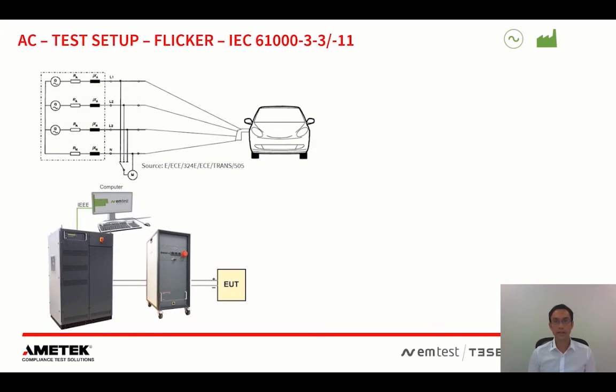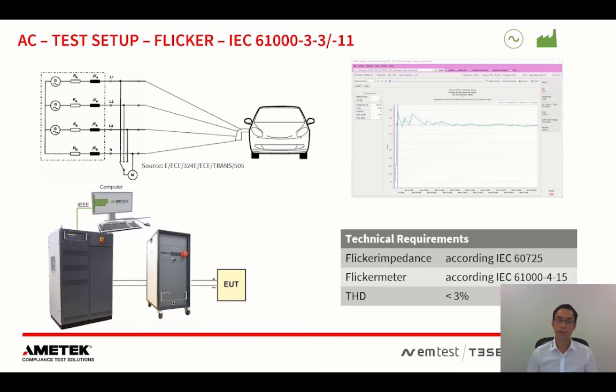The second test I want to highlight here is the flicker test, or voltage variations. It's a similar test setup to the harmonics, as you can see on the top left. Again, we have a three-phase or single-phase source that provides a very clean AC signal. We also have a measurement device, which is shown with the little M in the circle there. The measurement device, the so-called flicker meter, needs to be according to IEC 61000-4-15. There it is also very clearly specified how the flicker meter needs to measure. And then the special thing for flicker is that we have a so-called flicker impedance. That's an additional impedance that is introduced into the measurement circuit.